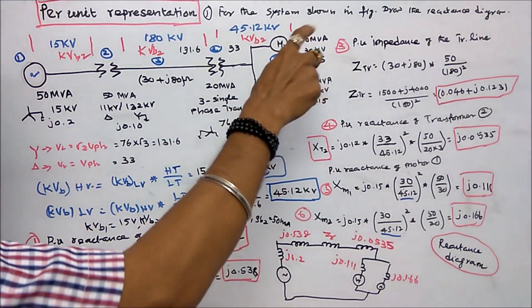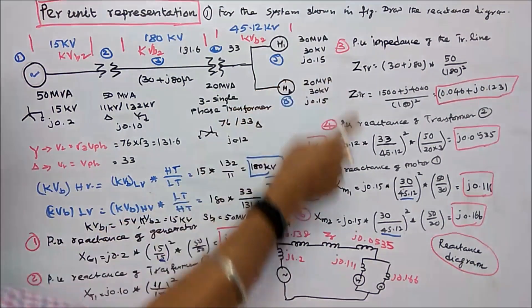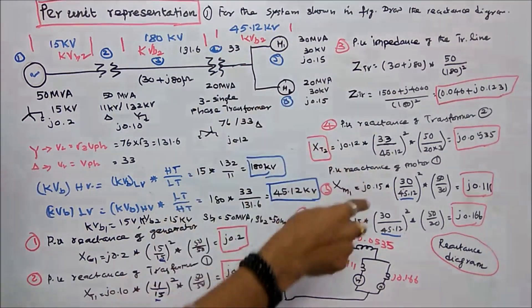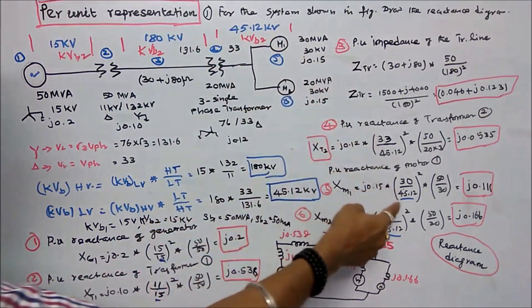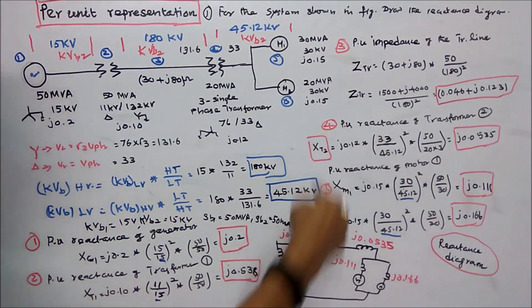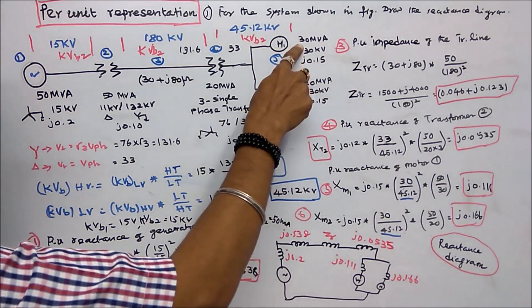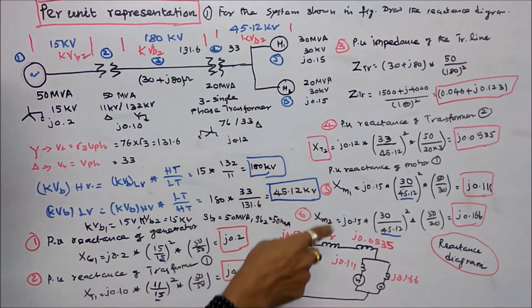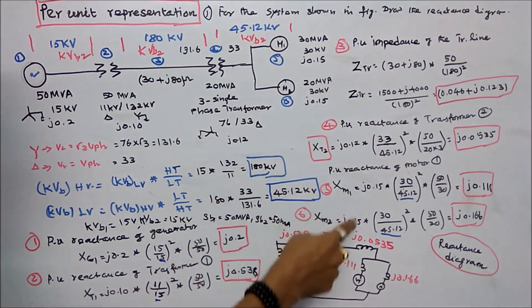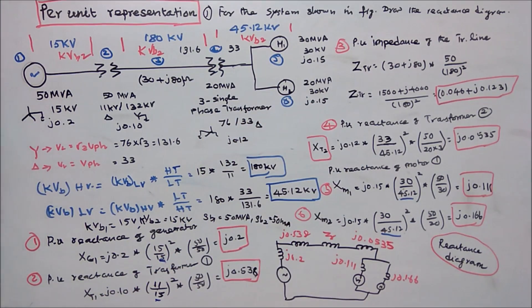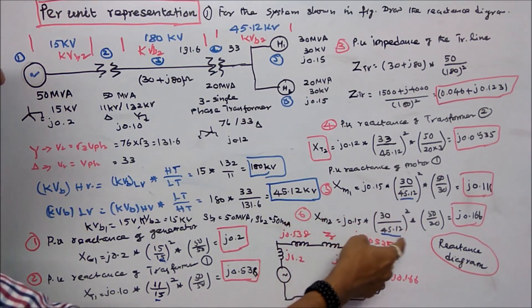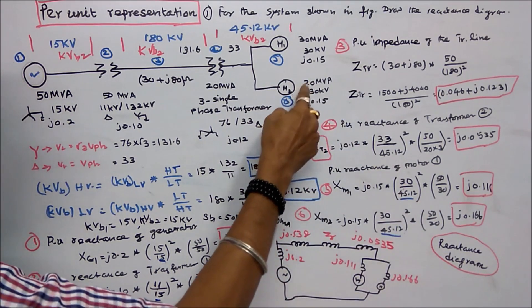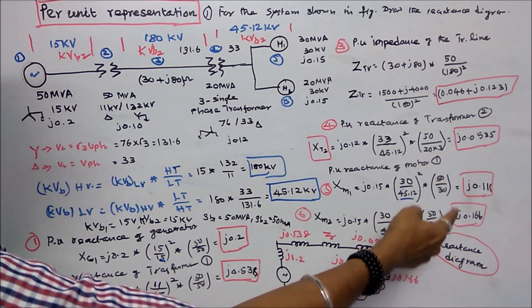Next is per unit reactance of motor 1, rated 30 MVA. Per unit equals J0.15 into (VB1/VB2) squared, that is (30/45.12) squared, times SB2 50 divided by given MVA 30. That equals J0.111. Similarly for motor 2, rated 20 MVA: J0.15 into (30/45.12) squared times 50/20. That equals J0.166.